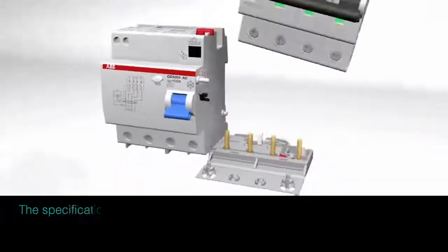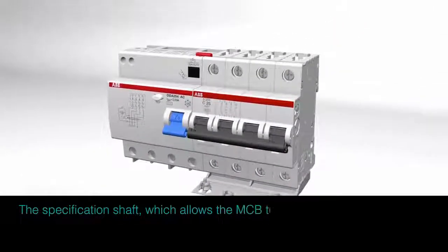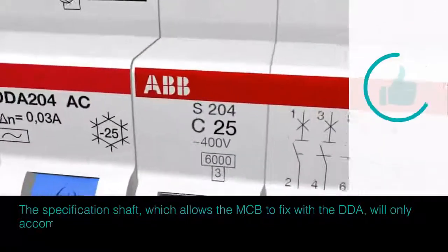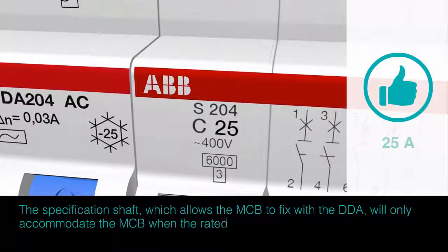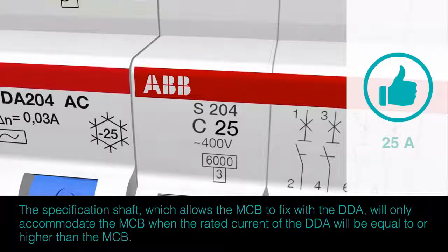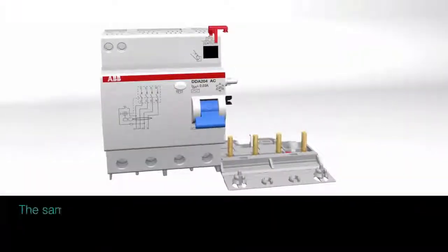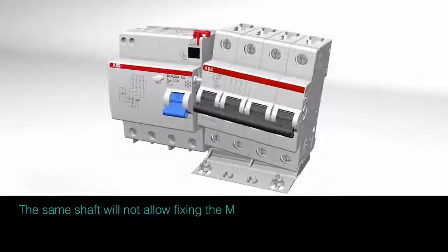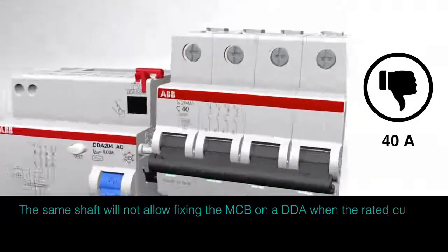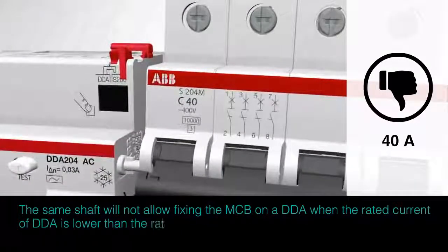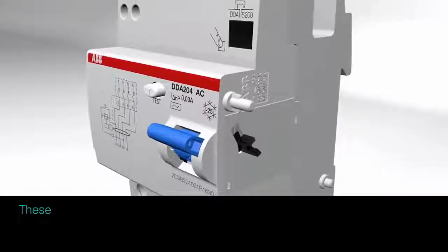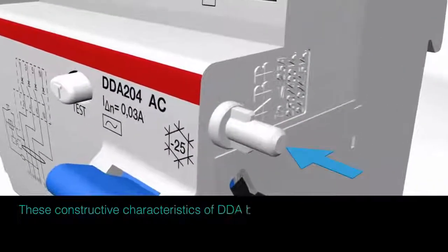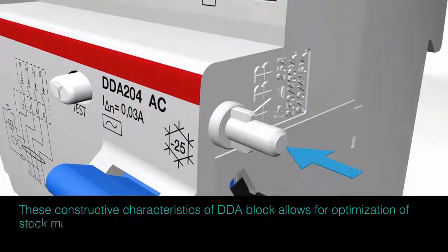The specification shaft, which allows the MCB to fix with the DDA, will only accommodate the MCB when the rated current of the DDA is equal to or higher than the MCB. The same shaft will not allow fixing the MCB on a DDA when the rated current of the DDA is lower than the rated current of the MCB. These constructive characteristics of the DDA block allow for optimization of stock management.